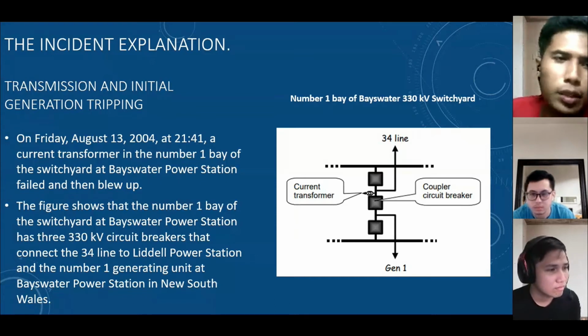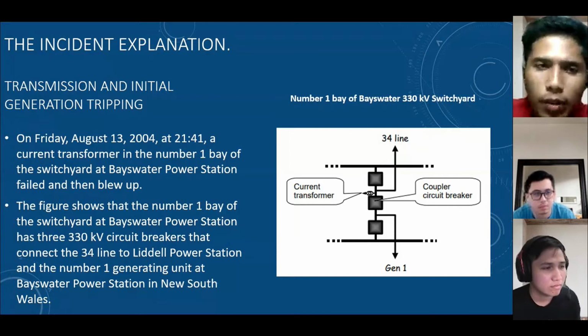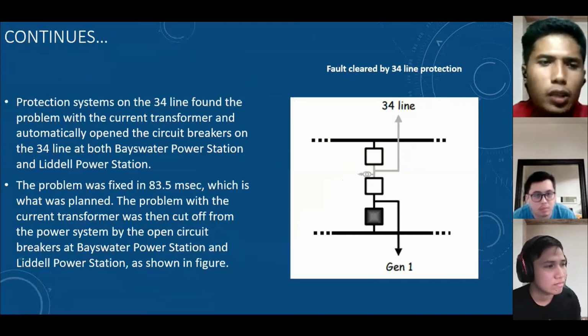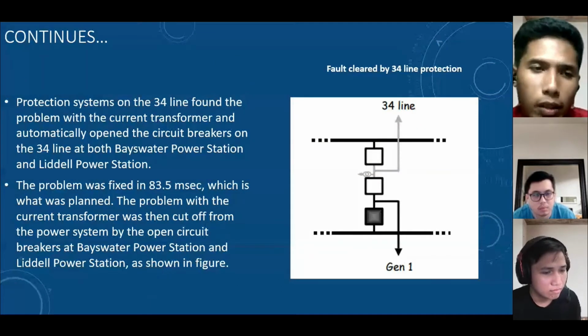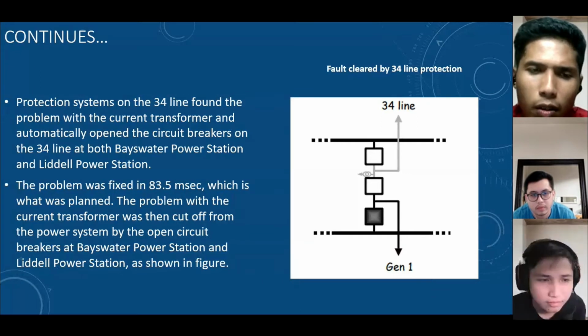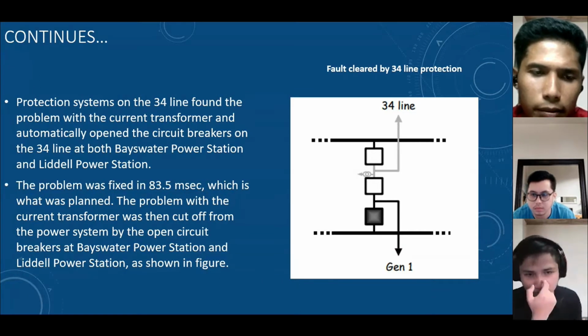Alright, next. The protective system on the 34 line detected the problem with the current transformer and automatically opened the circuit breaker on the 34 line at both power stations. The problem was cleared in 83.5 milliseconds, which was as planned. The faulted current transformer was cut off from the power system by the open circuit.